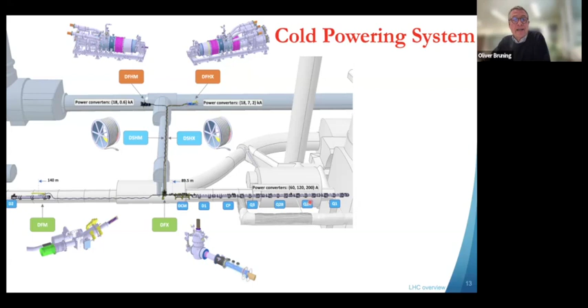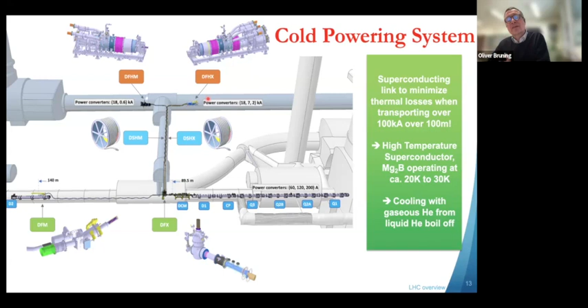So we took a high-temperature superconductor, magnesium diboride, which is capable of carrying over 100 kiloamps over 100 meters without any ohmic losses. It requires a cooling temperature of about 20 to 30 Kelvin, and you can provide that temperature by just boiling off liquid helium that we have in the magnets anyway, in the cryostats in the main tunnel. We let it boil off and the gas goes through this flexible cryostat up to the new galleries and to the feed boxes and makes sure that the superconducting cables are cool enough to be superconducting. And I will give you a couple more pictures later on. But that was one of the new technologies we had to develop for the high luminosity LHC.